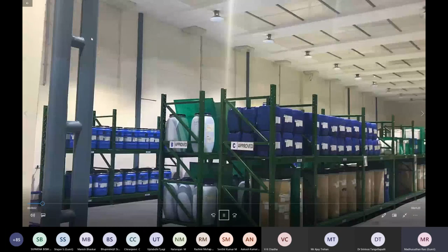I'll show another video of a different type of installation, an industrial warehouse where finished goods of a pharma company are stored. The original tonnage here was 130 tons. We completed the entire project within 72 tons, of which 26 tons is used occasionally, only for control of humidity. So primarily 50 tons is the sensible cooling required here.